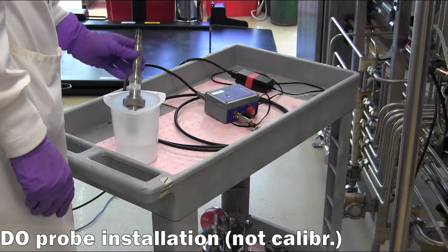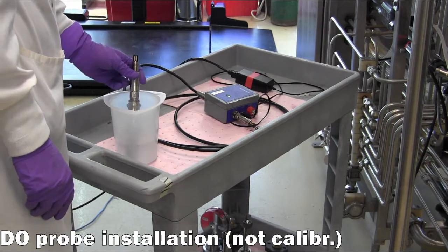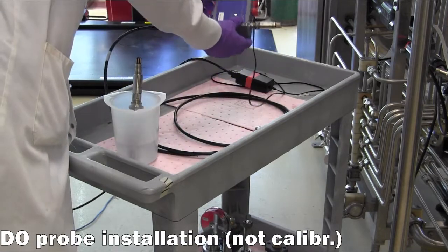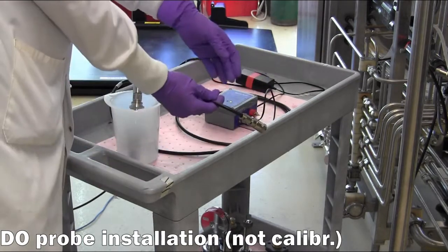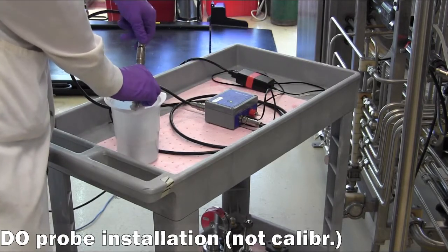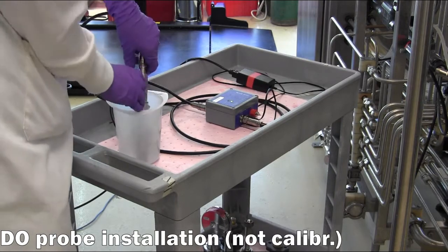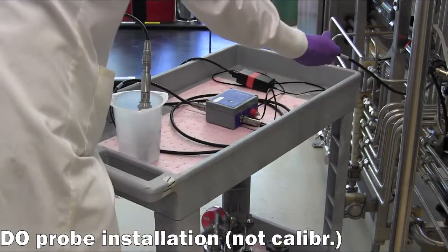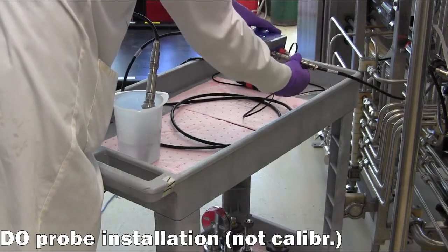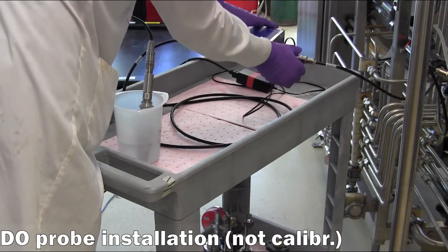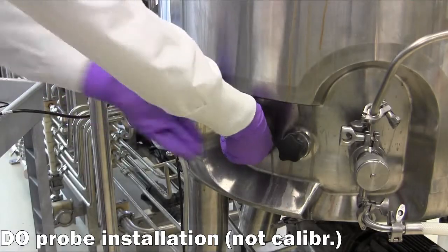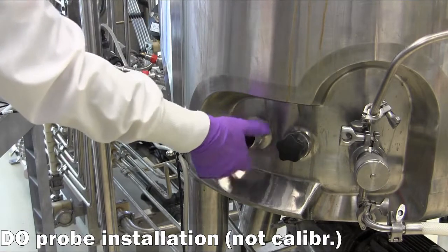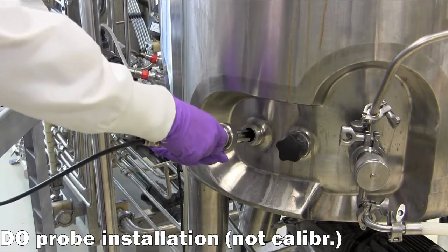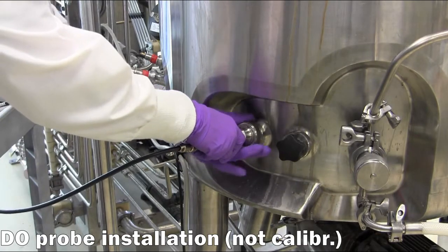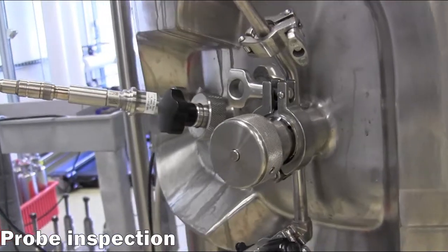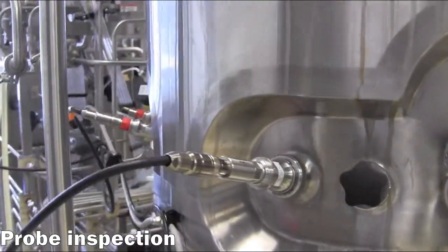The DO probe is installed without being calibrated. The DO probe also requires a signal converter from digital to analog. Plug the reactor line into the converter and the converter line into the probe. One final inspection, ensuring the transmitter lines and the probes are secured, is always good.